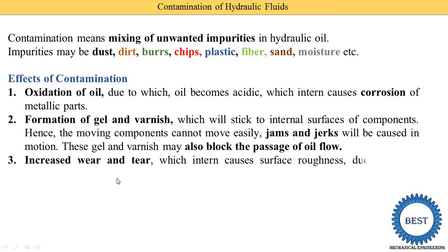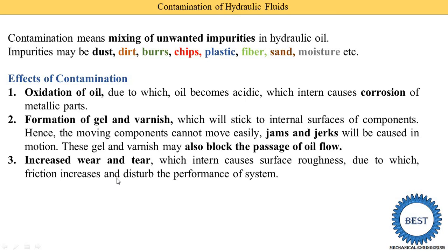The next effect is increased wear and tear. Due to contamination, wear and tear increases in the hydraulic system, which in turn causes increased surface roughness of components. This increased roughness leads to increased friction, which raises the temperature of the oil and disturbs the performance of the system.